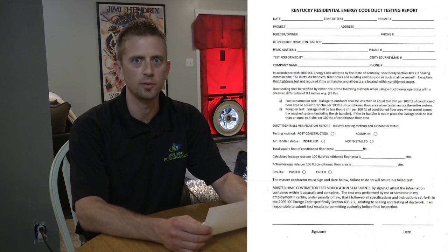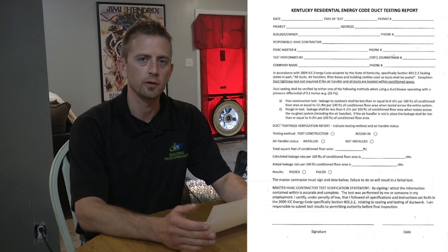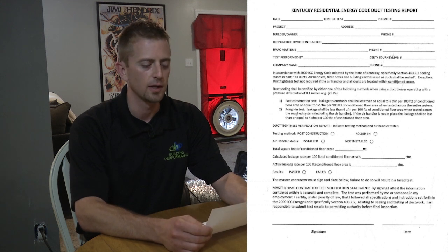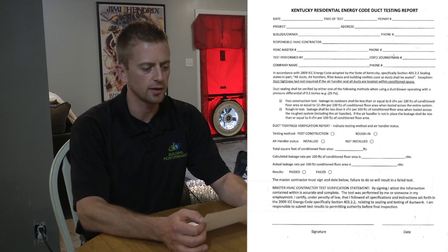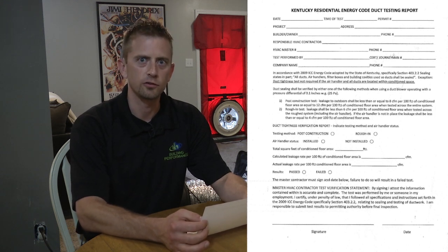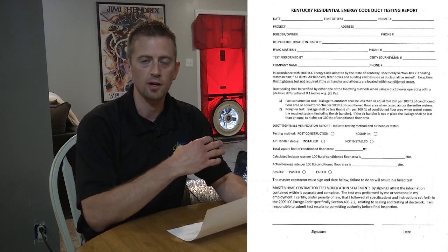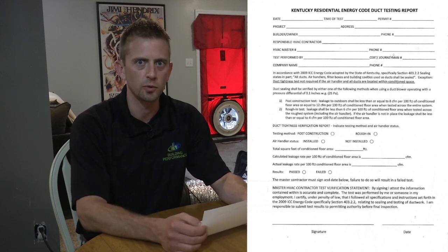So now that we got the duct leakage test done, we need to fill out a report for this house. The report needs to be given to the builder as well as the building inspector for the code compliance verification. So in Kentucky, we have a nice little form that was created for us. You can also use a form that is generated from the equipment. There's software that comes with the equipment, and that's approved as well.